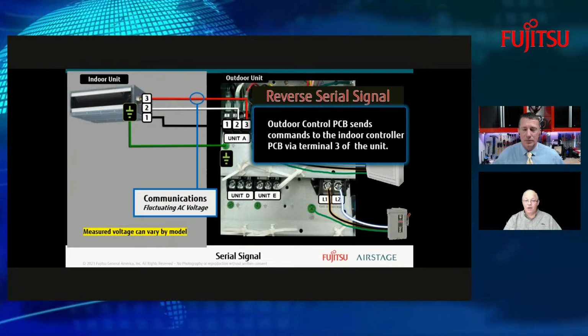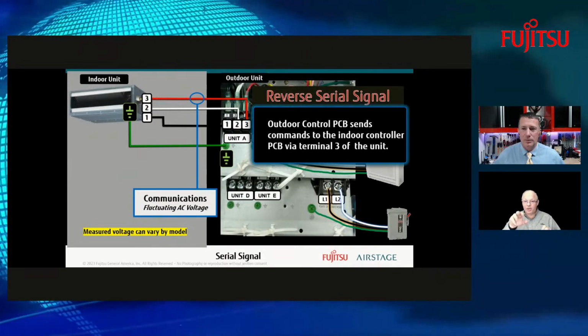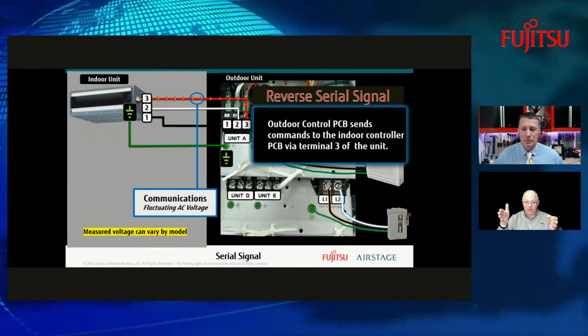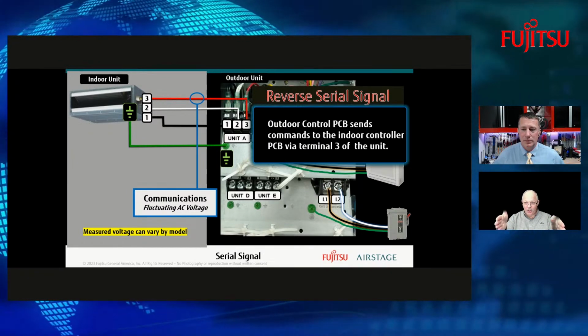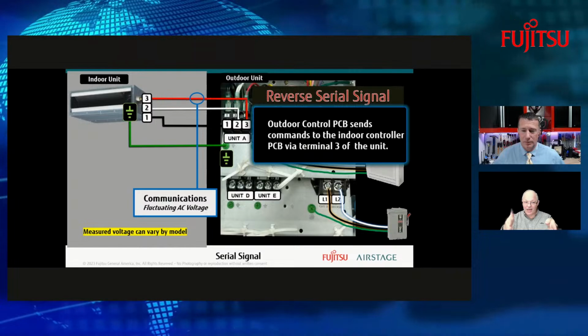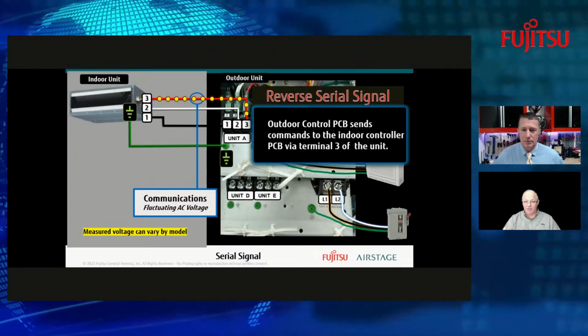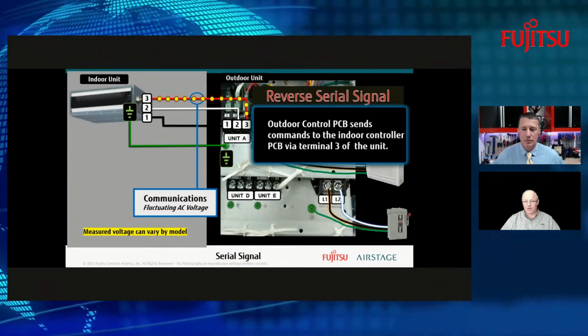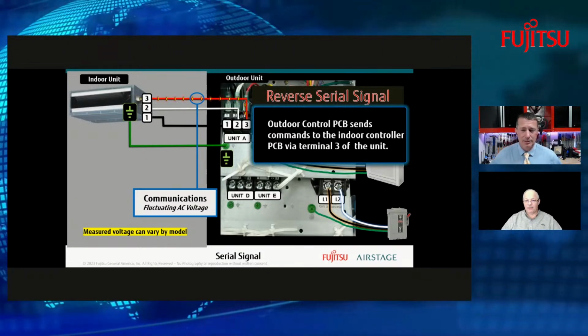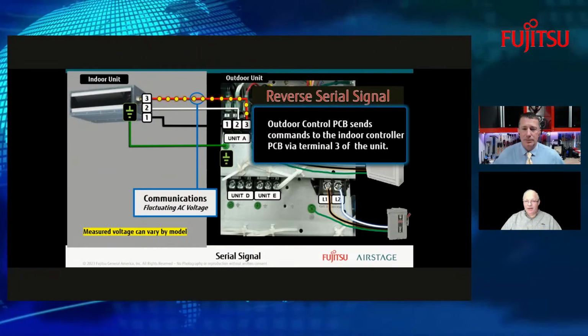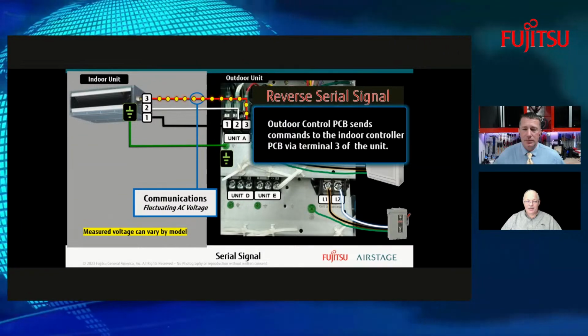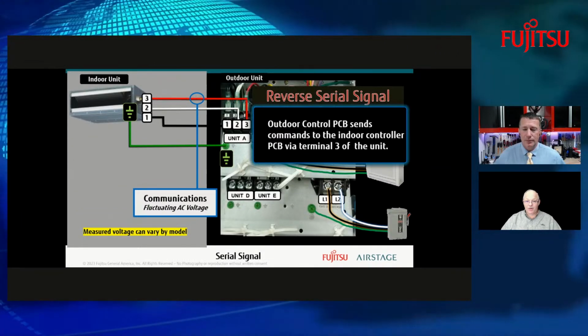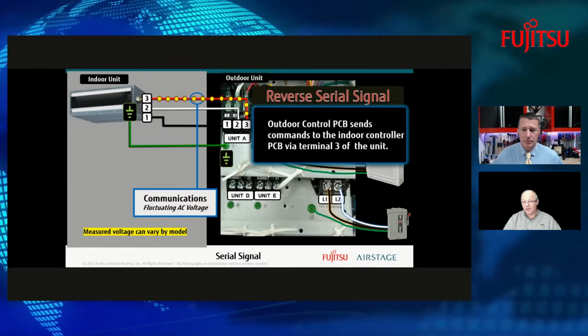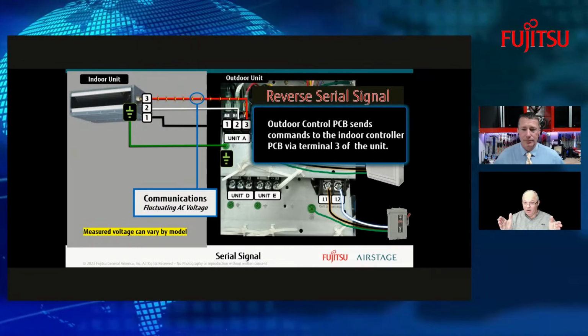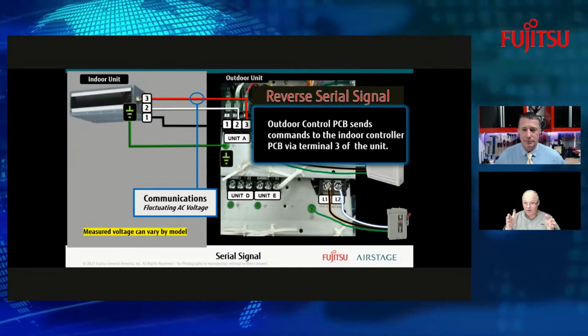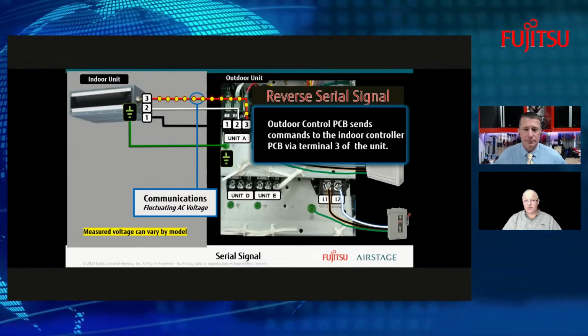Then I'm like, okay, now let me look for the biggest number, and I'll see it jumping around, and I look for the biggest number. And as long as I'm within the range, then I'm good. If I get outside of that range, then I'm probably going to end up looking at replacing the board. And what would that range be? It could vary. It could be anywhere from maybe 60 to 130, or it might be 30 to 160. It depends on the model. Depends on the system. Yeah, but your eyes pretty much have to make sure it stays within that range. Okay. So just how good are your eyes?